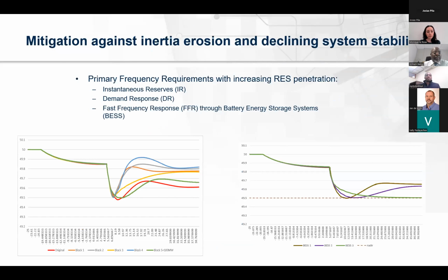Okay, so obviously, as you can see on the previous slide, as renewable energy increases, there's an inherent risk that the system might become a little bit more unstable, but you can mitigate against those. And that's also part of the study that we looked at: the mitigation against inertia erosion and declining system stability, what can be done for that. So then we look at future network scenarios, what needs to be brought online to keep the system stable so that you can keep the system frequency within the stable range. Some of the mitigation measures are instantaneous reserves, that's the reserves in the generators that can be used to keep the system stable, and then demand response measures, which basically equates to load shedding or the under frequency load shedding scheme that will operate to keep your system stable and your frequency within that band.